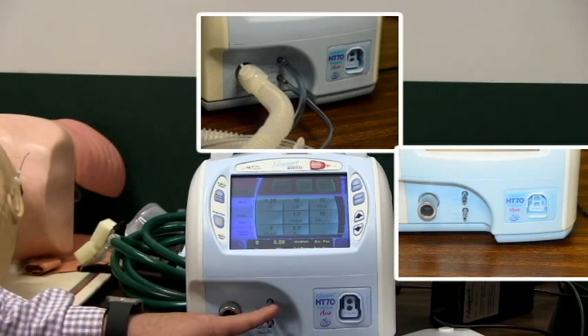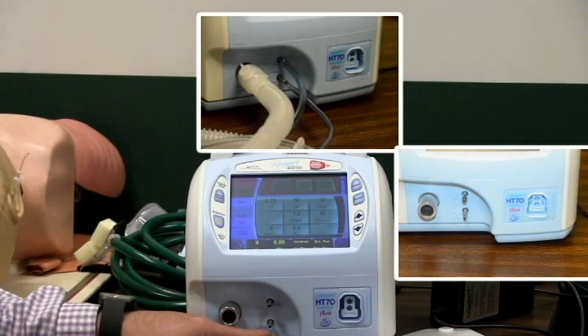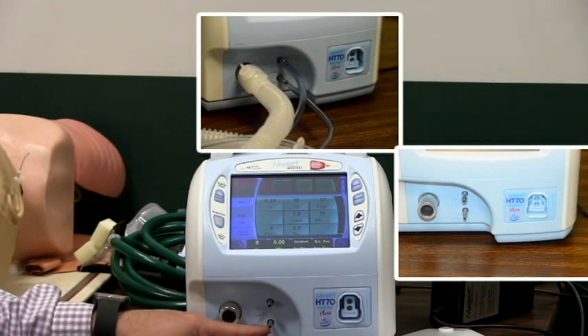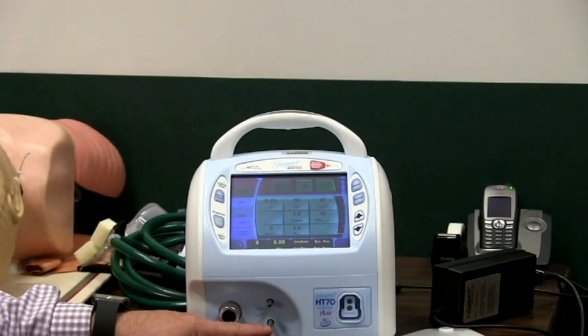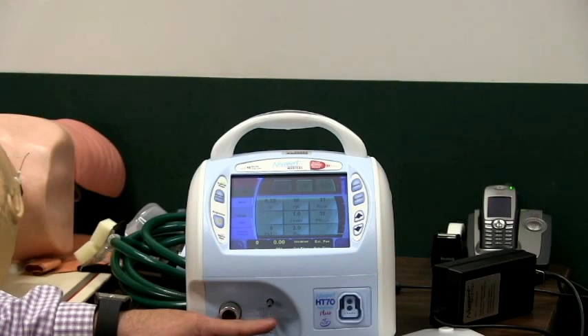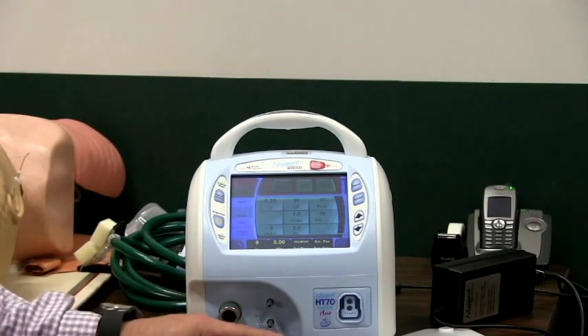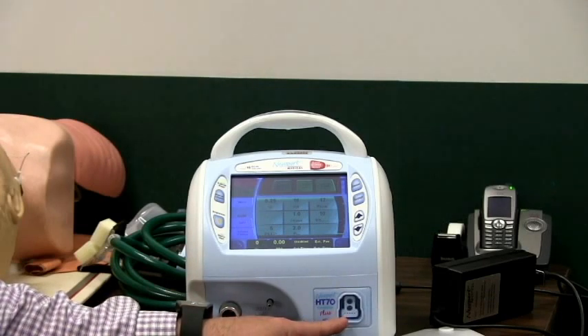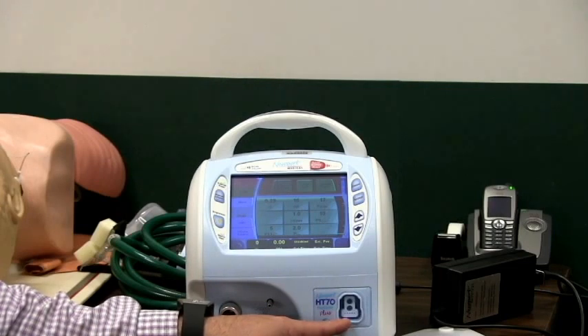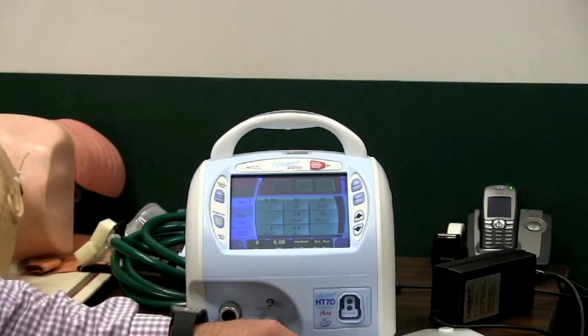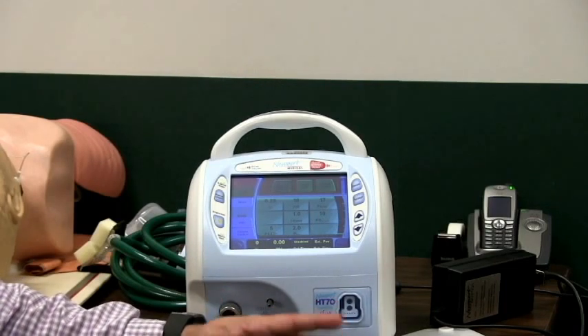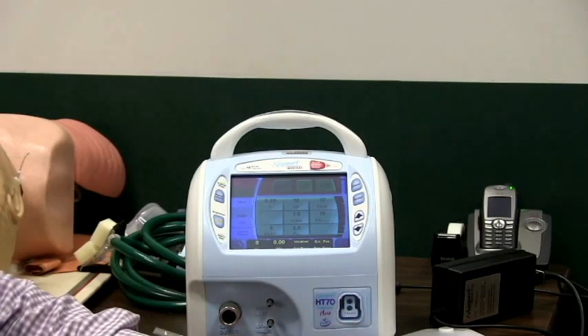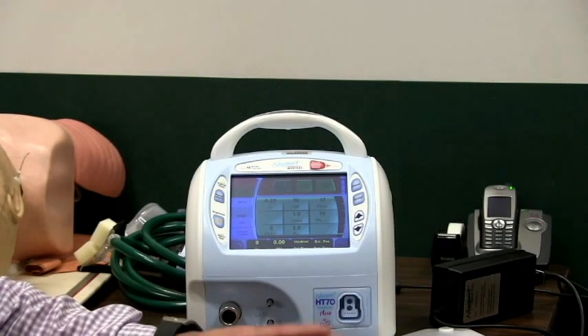On the top portion here on the other side you have your Prox Airline, which is a larger diameter plastic hose that's associated with the circuit. And then you have your exhalation valve circuit connector here that is a smaller diameter hose. Again, I'm sure if you push hard enough you'll get either one to fit on there, but make sure that you pay attention so that it's connected correctly. Over here you have your flow sensor. Again, we do not utilize flow sensors here. It's not advantageous for us and is probably a little more inhibitive during a transport setting than anything else, because it is much more sensitive for the patient. But in a traveling mode, simple things like movement and cardiac oscillations can trigger the vent in the wrong position to deliver ventilations when maybe it's not needed.